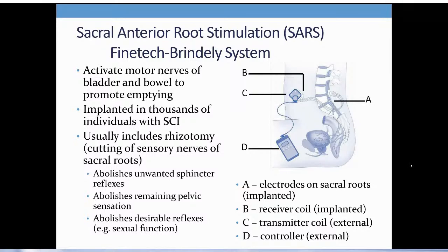And they'll turn the controller on to the program for, say, emptying their bladder. Then it transmits a signal through the coils to the leads and then to the electrodes, which will stimulate the sacral roots with the appropriate pattern to get the motor efferents to drive the bladder to contract. And so this is a device that gets the bladder to contract on demand.